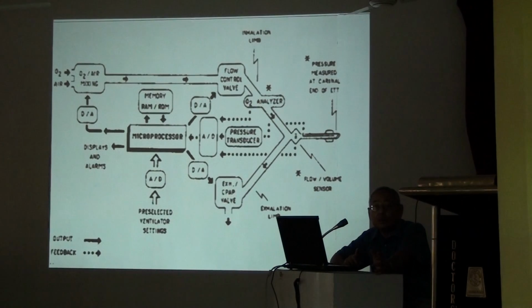I am reminding you, this total ventilatory technology is only for inspiratory maneuvering, nothing else. The exhalation, we don't have to do anything. We depend on the patient's own elastic recoil of the lung. So when air starts to come out, it means you have to stop this inspiration somewhere. If you continue to flow continuous air from this valve, then what will happen? The patient will burst. So you have to stop this valve at some point of time. That will be taken over by the inside machines. Then the exhaled air will come out swiftly.